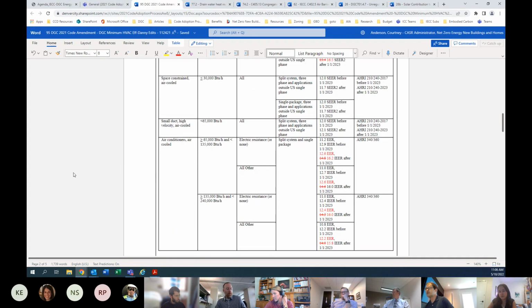Great, that's good. And then similarly for the larger air conditioners between 65 and 135 kBtu per hour, and also the larger ones, 135 to 240, there are some similar changes made to both. Now these larger equipment have both the EER, which is a full load rating. It's meant to represent roughly a design test condition, the rating procedure at 95-degree dry bulb ambient temperature and running at full load, whereas the IEER is a composite of four different rating points that's meant to be more of an annual metric. And where the equipment manufacturers have really made some gains, through staging of compressors and equipment and through controls, is in the part load metric, the IEER.